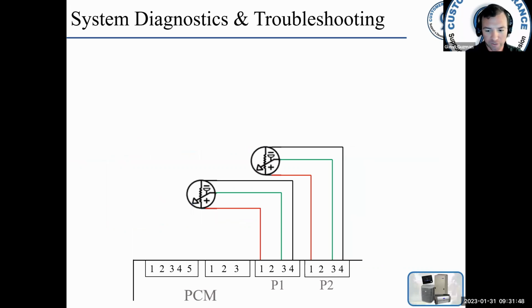Transducers. I told you before, you have two transducers on this unit, P1 and P2. The transducers are installed on the suction line and the discharge line of the compressor. Transducers have a sensing range of 0 to 620 psig. The connection points of the PCM are labeled P1, P2. The two connection points are identical, and either pressure transducer can connect to either input. The software in the PCM detects which transducer is connected to which input and assigns the signals accordingly.